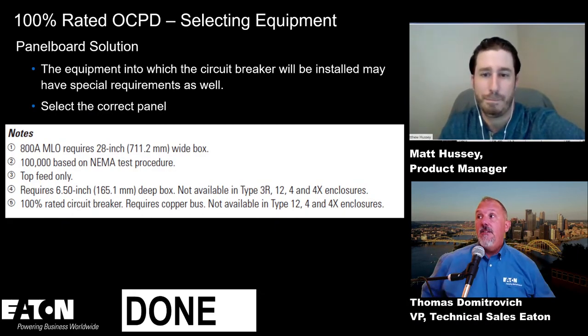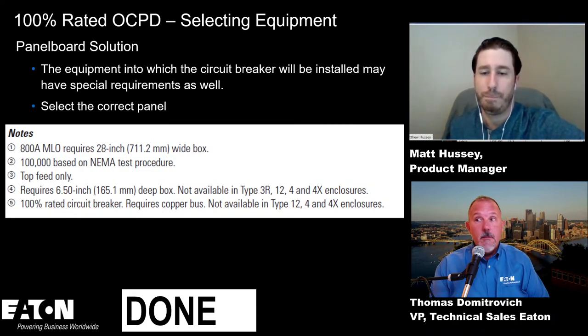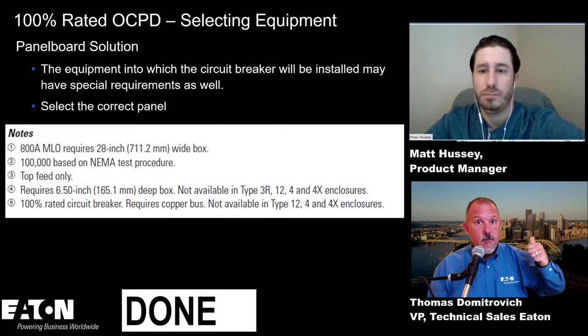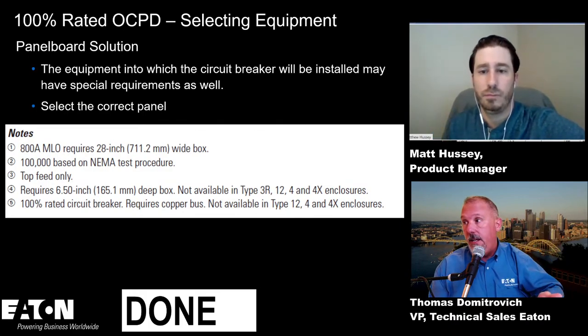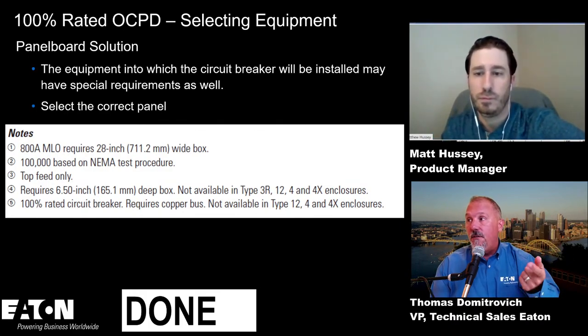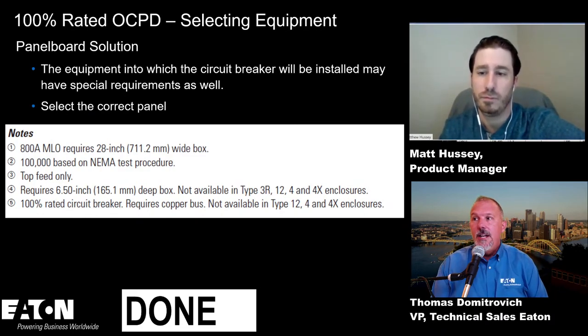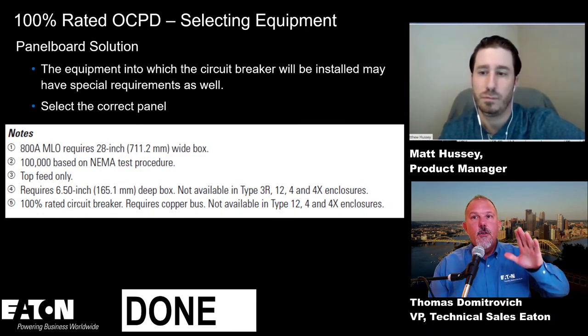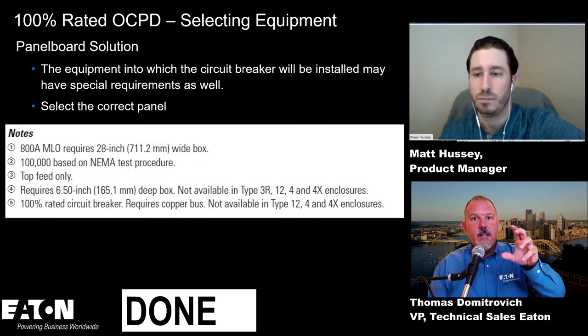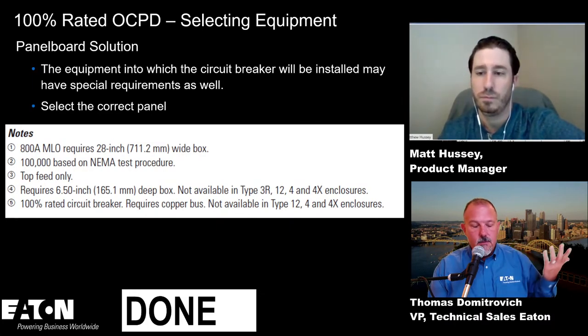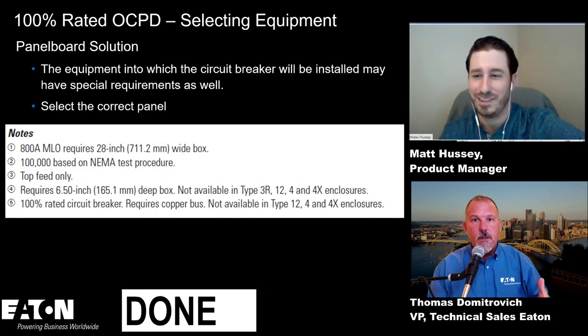This right here is from our panel board solution. It talks about a 100% rated circuit breaker requiring copper bus. And we saw that in the standard, right? Because that's how we test 100% rated. And it's not available in a 12, 4, and a 4X enclosure. So in some cases with your panel boards, you've got to look and see what steel can I wrap around that overcurrent device? Is it a specific panel board?